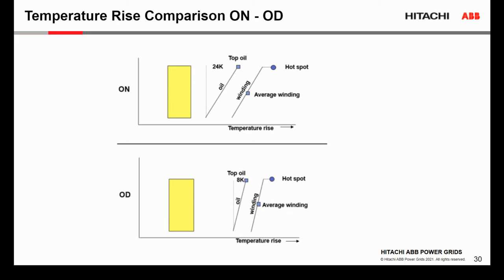For transformers with directed oil flow, we see very little difference. Usually it's in the range of 5 to 8 degrees C. And also the gradient between the winding and oil is much lower in transformers with OD cooling compared to transformers with ONAN and ONAF cooling.